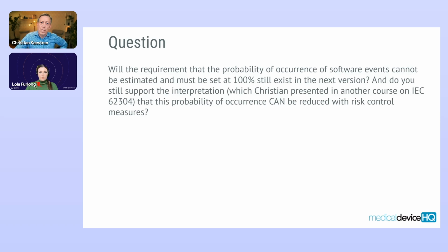This one is longer. Will a requirement that the probability of occurrence of software events cannot be estimated and must be set to 100% still exist in the next version? And do you still support the interpretation, which Christian, and by the way, thanks for putting me on the spot, presented in another course on IEC 62304, that this probability of occurrence can be reduced with risk control measures?